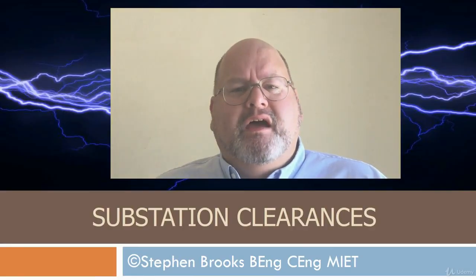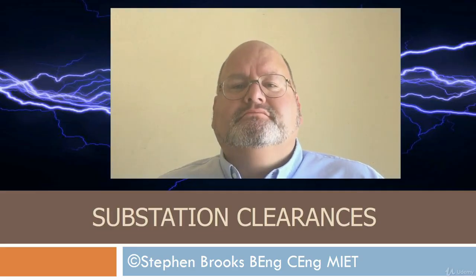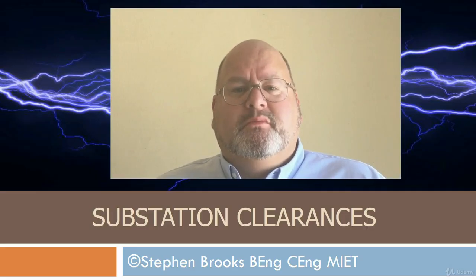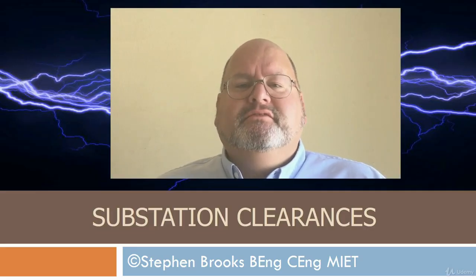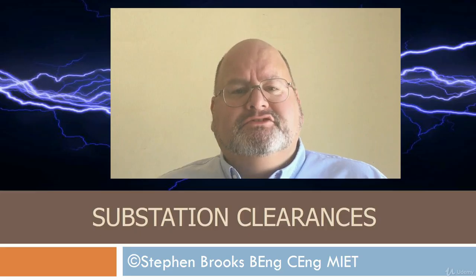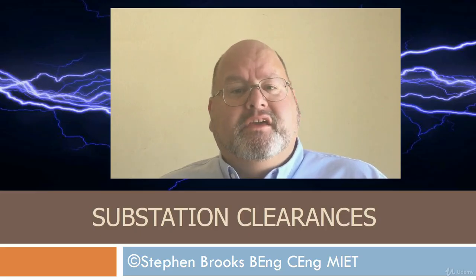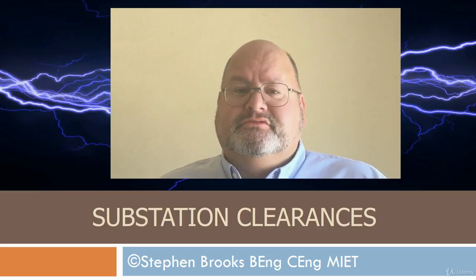Air-insulated substations use air as an insulating medium, and therefore need to be designed carefully so the electrical energy that passes through them is controlled and kept safe. To do this, we space the equipment out using electrical clearances. By the end of this section, you'll understand what the main electrical clearance parameters are and how they are used to design the substation.